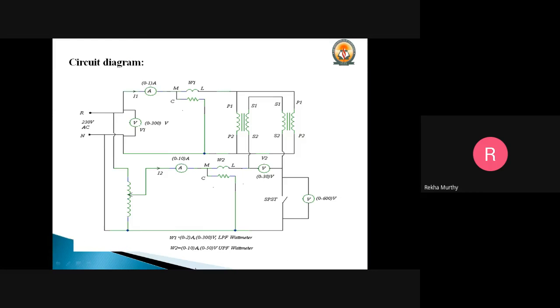Now let's look at the circuit diagram. This part of the circuit is nothing but similar to the open circuit test conducted in the first session. The lower part is almost a copy of the short circuit test circuit diagram. The secondaries (S2) of the first transformer and the second transformer are connected to the voltmeter. That is the only difference — the remaining connections are the same as in the OC and SC tests.